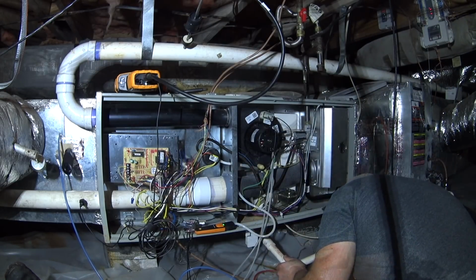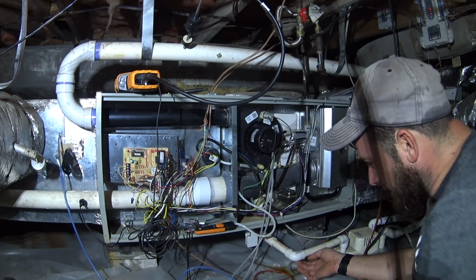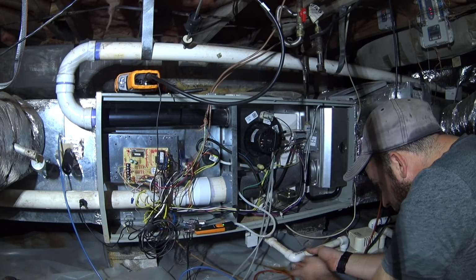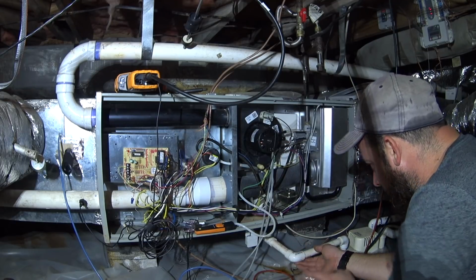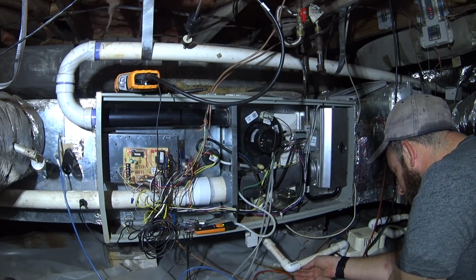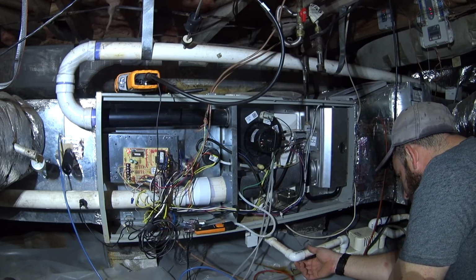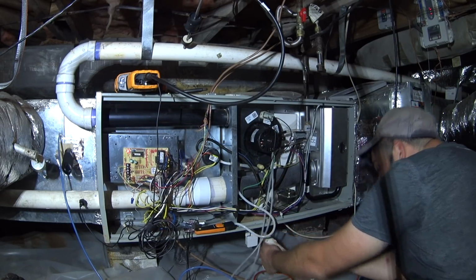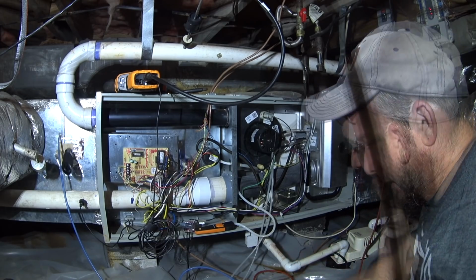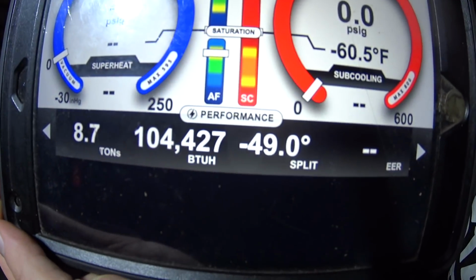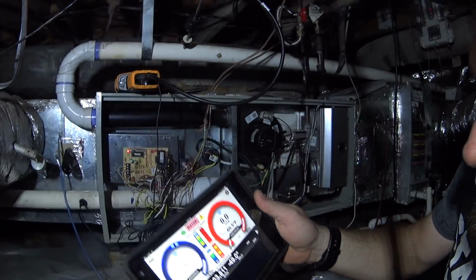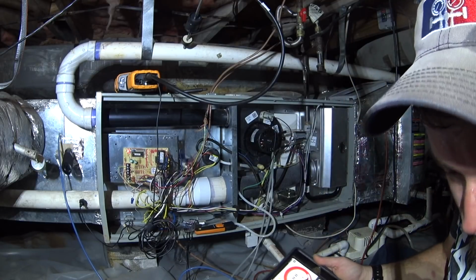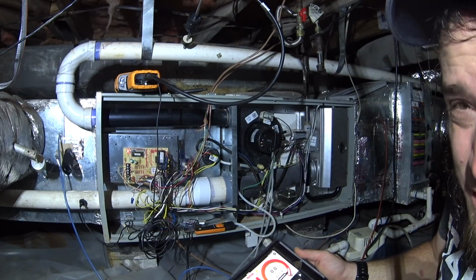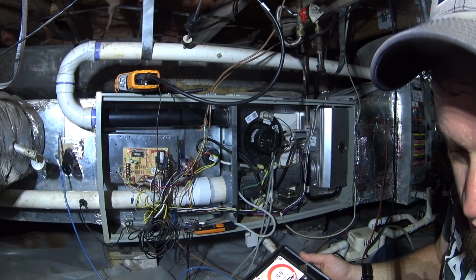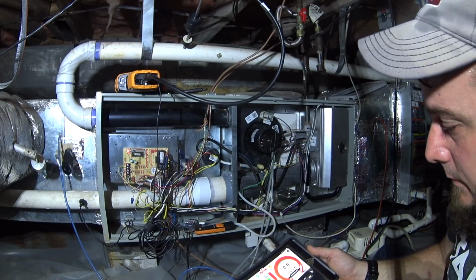It looks like we're actually double trapping this drain on the furnace a little bit. When this elbow sags down, it leaks water back here where the hose clamp is connected. Alright, we've got balanced temperature at 49 degrees. I'm going to go clock the meter, and I'm not going to take you with me on this one. If you'd like to see that happen, I've got several videos that posted recently.